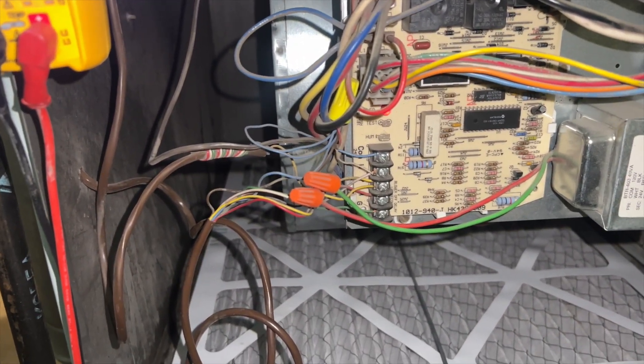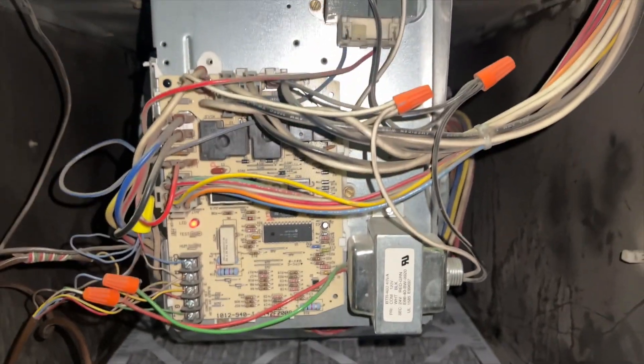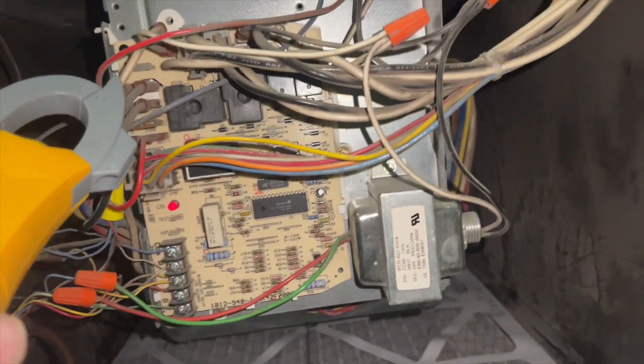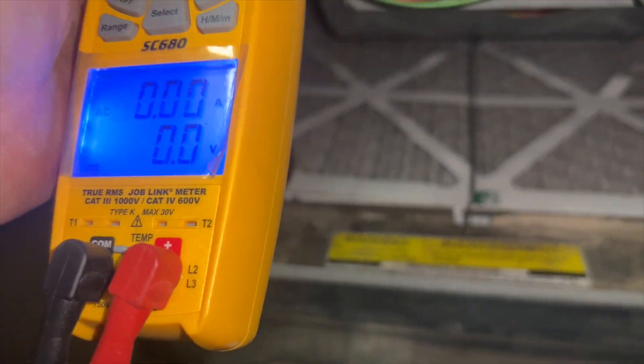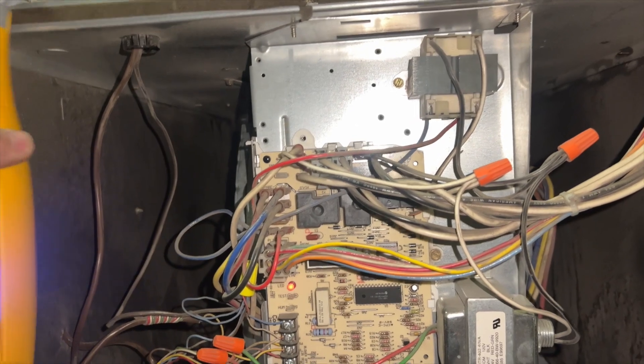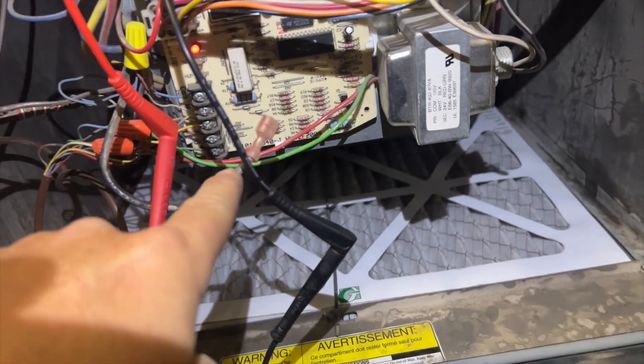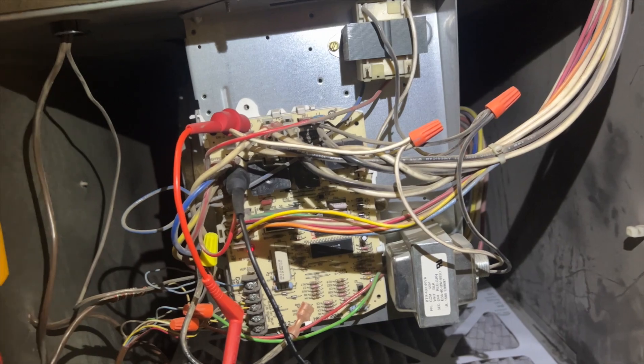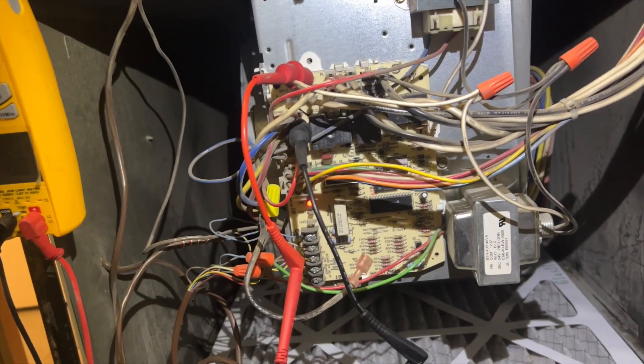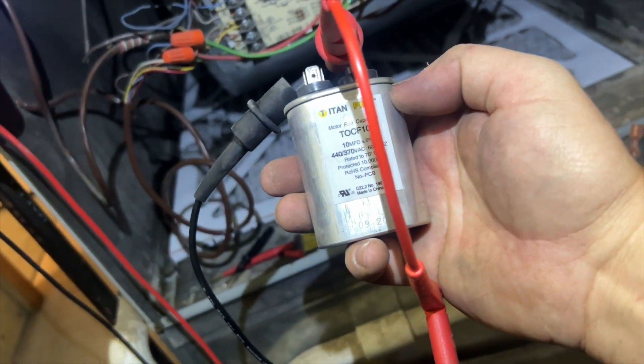When I pull this panel off I can smell chemicals burning, so I suspect something is wrong with the blower motor. Let's check for amp draw on the blower motor using the common wire — we have zero amps. Now we check for voltage going to the blower motor. I've unplugged the common wire (black) and the neutral, and we're getting no voltage. We might have a bad relay on the board.